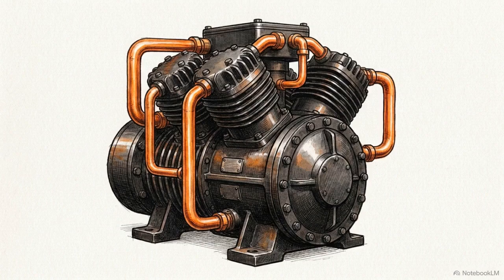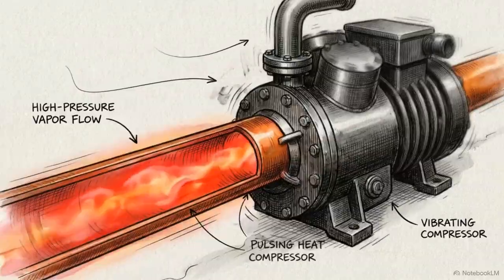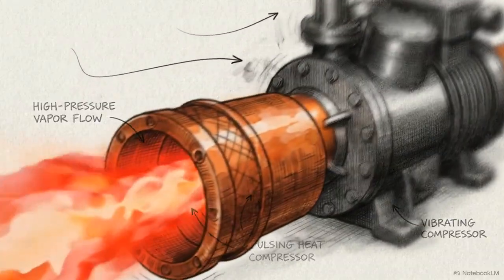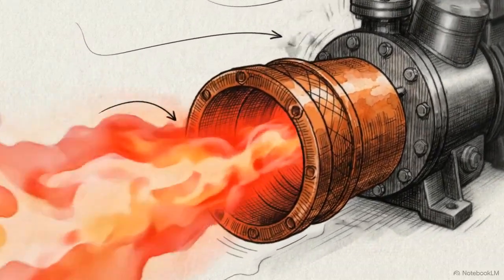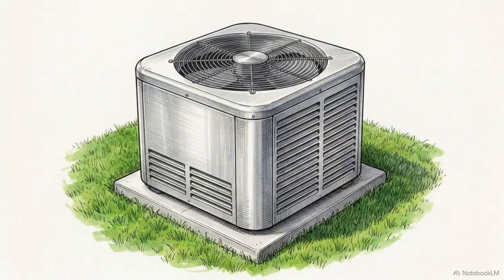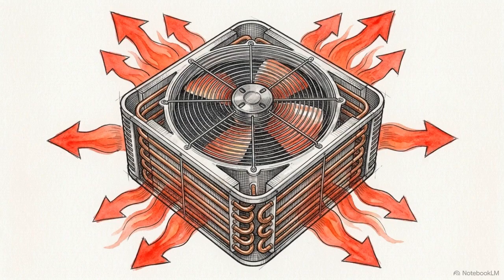You can have the most powerful compressor in the world, aggressively pumping refrigerant through your system, but it will never drop the temperature of a room by a single degree unless you have a mechanism to eject that heat. That mechanism is the condenser. It operates strictly as a specialized heat exchanger, engineered with a single objective: continuous heat rejection.